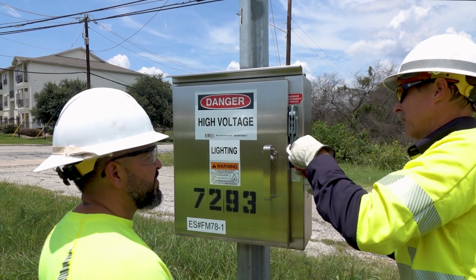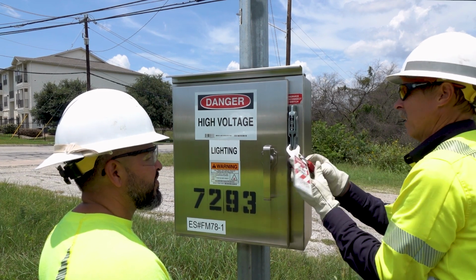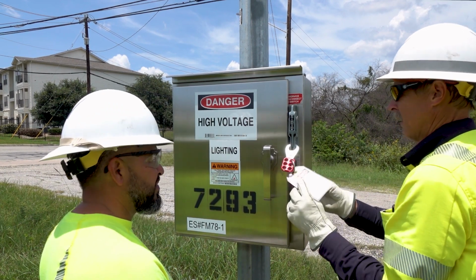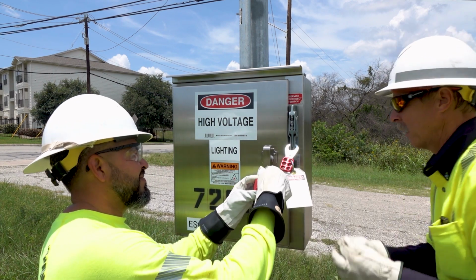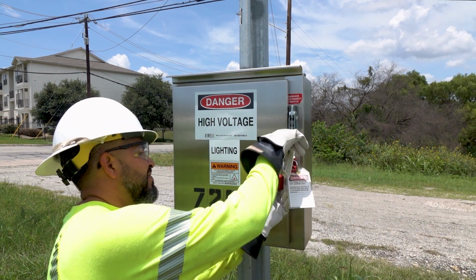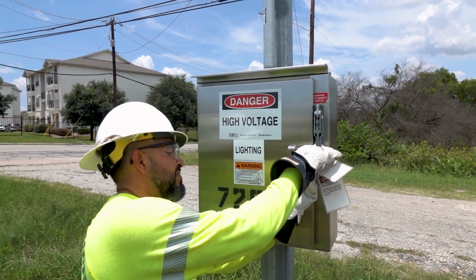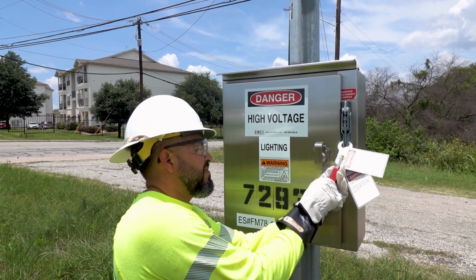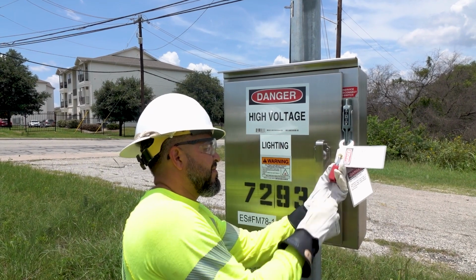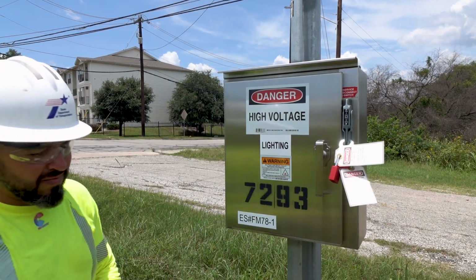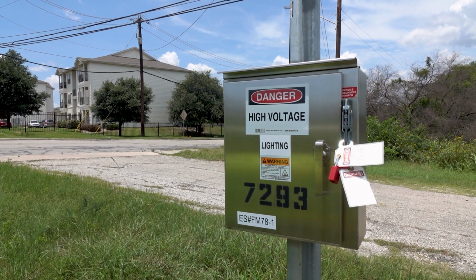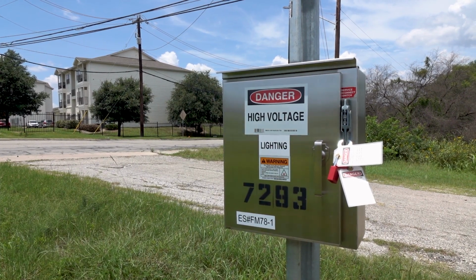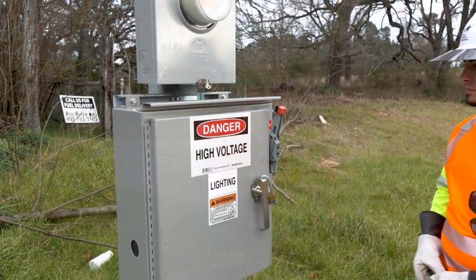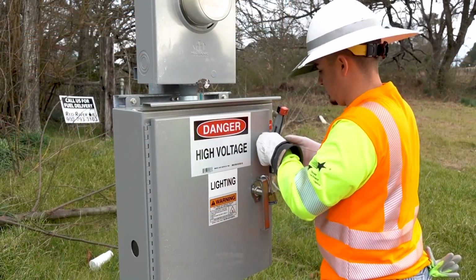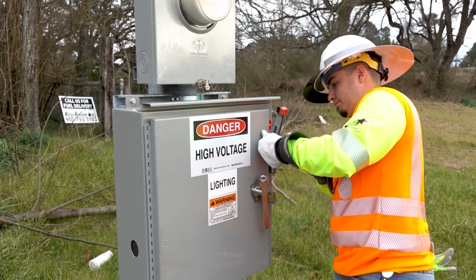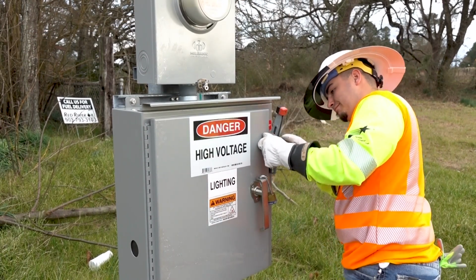It is best to perform most of the service inspection before power has been applied. Sometimes this is not possible. Once a service has been energized by the utility company, proper lock-out/tag-out procedures must be followed before the service's enclosure door can be opened. The lock used by the inspector for lockout should be one that no one else has the key or combination to. The padlock and tag must be installed if the inspector is going to be away from the service location. After inspection and the service is energized, the contractor must lock the enclosure with a master padlock keyed for number 2195.